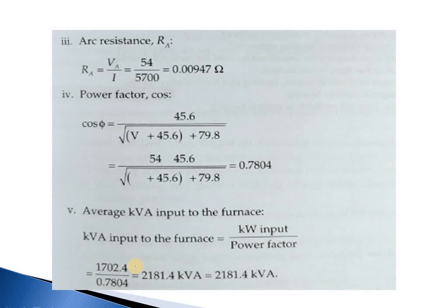Thirdly, arc resistance RA equals VA by I, which is 54 by 5,700. We are getting 0.00947 ohm. Fourthly, power factor cos phi, we have calculated. We are getting that the power factor value is 0.7804. Next, average kVA in the furnace, that is kilowatt input divided by the power factor. So the value is 2181.4 kVA. So these are the four values we have calculated from this topic.